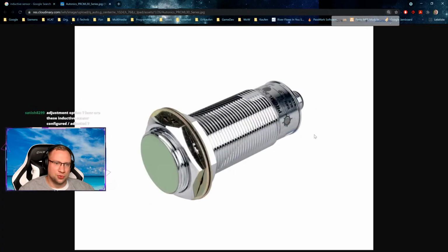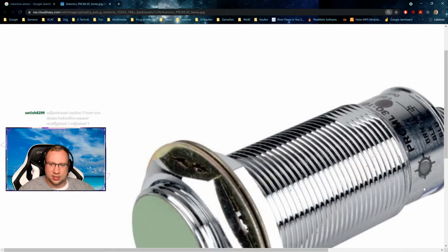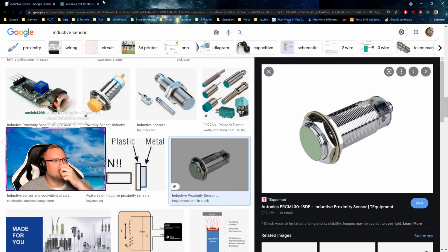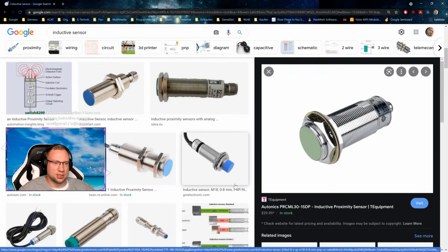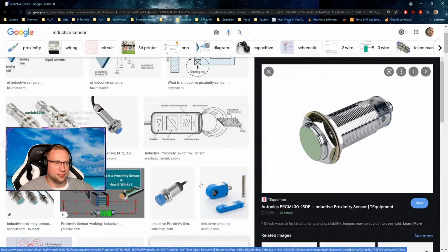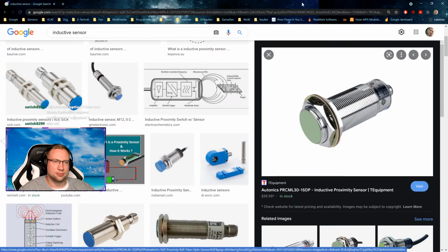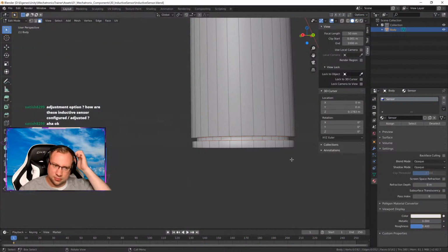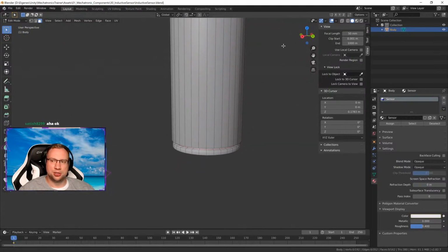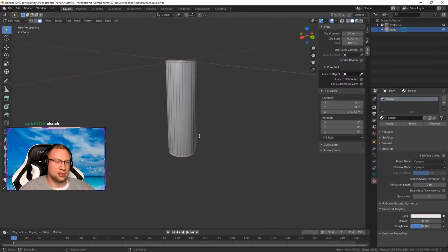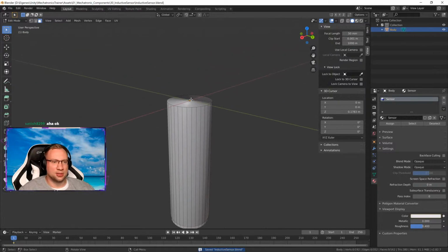Oh, that's not a screw, but sometimes there's a little screw here, and you can adjust the range a little bit with it. Not too much though. Depends on the sensor as well. Most of them don't have it. You buy them for a specific distance and then it's fine. Some of them also have a teach function that comes with it. It really highly depends on the sensor.